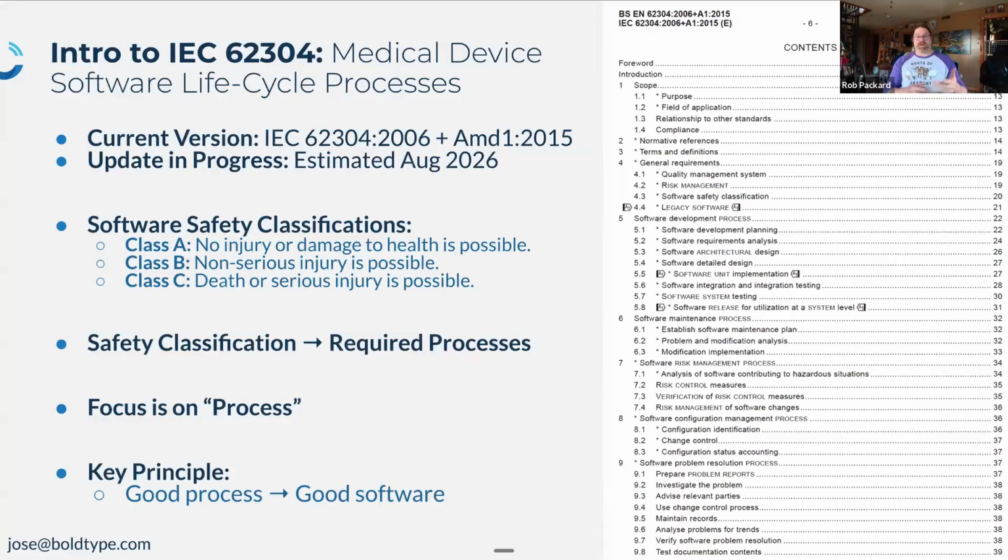They might have them as a class 1 510(k) exempt, but if they're reviewing it as a 510(k), it's probably not a class A. Just a rule of thumb. Less than 10%, single digits. The class C, that's not the case. There are a lot of products out there that the FDA definitely thinks are class C. You and I might not agree, Jose, but the FDA wins on a lot of these.